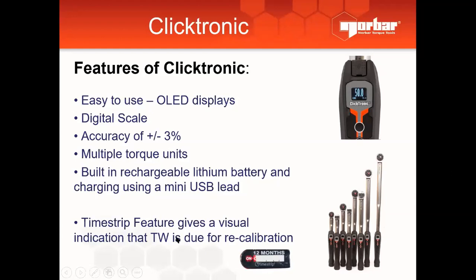It comes with timestrip. Time stream shows you an indication of the time where you can see 1 line, 2 line, 3 line. So this is 3 months, 6 months, 9 months, showing when it's due for calibration. So whenever the user starts using it, they can check the indications first, whether it's still valid or due for calibration.